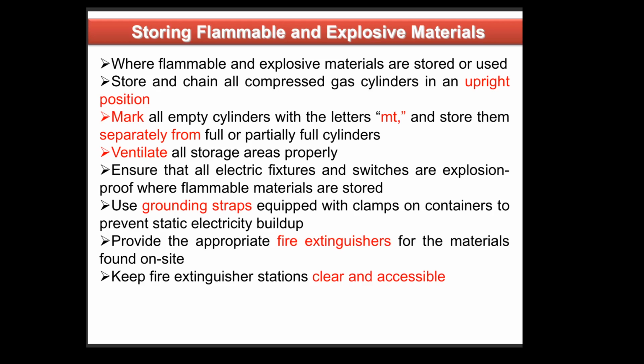Mark all empty cylinders with the word empty and store them separately from full or partially full cylinders. Ventilate all storage areas properly. Ensure that all electric fixtures and switches are explosion proof where flammable materials are stored. Use grounding straps equipped with clamps on containers to prevent static electricity buildup. Provide the appropriate fire extinguishers for the materials found on site. Keep fire extinguisher stations clear and accessible.